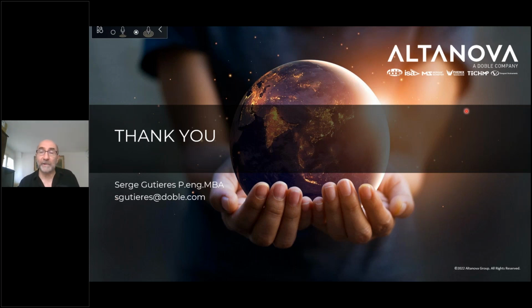Well, it depends on which one you're using. Let me see if I can. Cannot. My presentation is frozen. Depending on whether you're using the Doble or, as I say, usually people are using the IEEE. If your gas level reaches the upper level of condition 3, or if it's in condition 4, usually that means you have a serious problem. You look at the gas levels, especially the acetylene and the ethylene, they're very, very high.